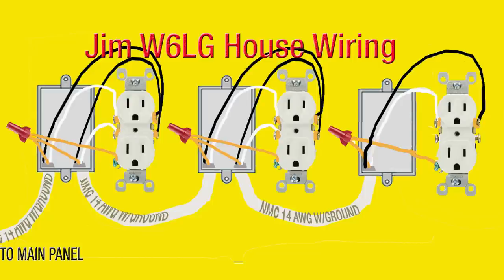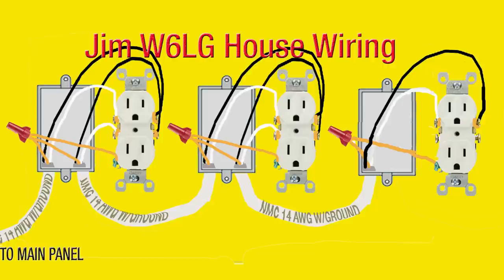The electrical outlets in my house are pretty much all connected the same way. A non-metallic cable, happens to be 12-gauge for all outlets. The beginning of that run goes to the first electrical outlet, to the two screws. The remaining two screws connect to the next line of Romex. It goes to the next box, and that's chained as it goes down until it gets to the last outlet. The grounds are all tied together, either by twisting and a wire nut, or just by a wire nut. That's how I chained each of the outlets together, and pay particular attention to that ground connection. That's pretty typical for most houses.